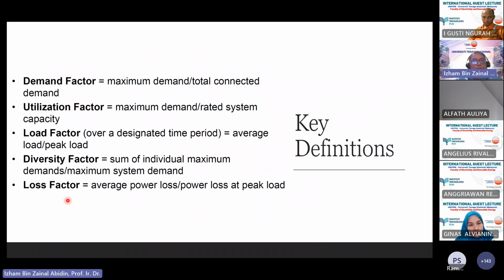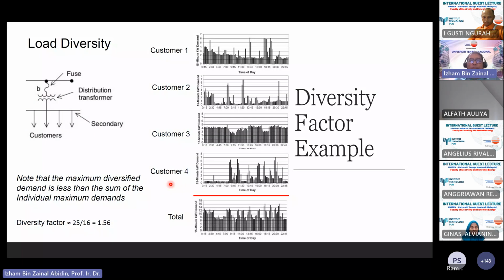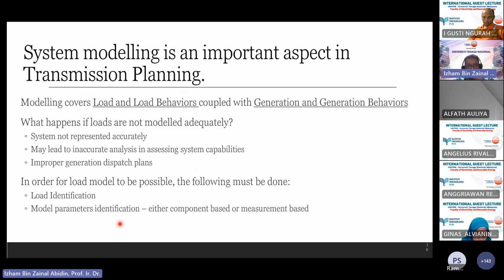If you look back at the formula here, diversity factor is the sum of individual maximum demand over maximum system demand. So each of these has its own maximum demand here, here, here, and here. You add all those maximum demands and divide by the total system maximum demand. So in this case, diversity factor is 1.56. These are some examples just to understand load diversity.